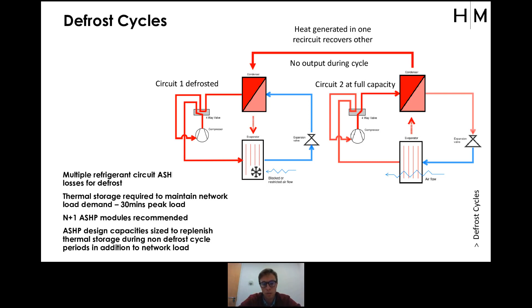The other key consideration here is when you're in defrost, you're obviously using up your energy reserve in the thermal storage. You need to then replenish that, and that may be during a peak scenario. So you need to allow for enough capacity in your air source heat pump to not only meet your peak, but to replenish your systems just in case you have a very flat peak. But that could all be analysed in detail if you don't want to oversize your system as well, and then you have impact on your efficiency.